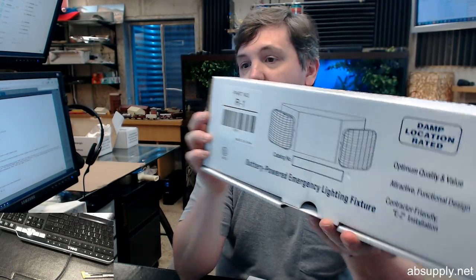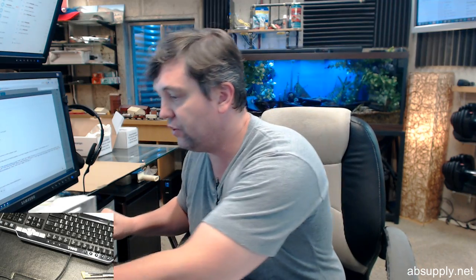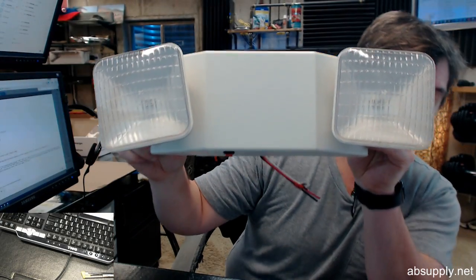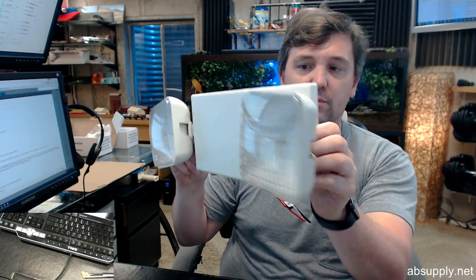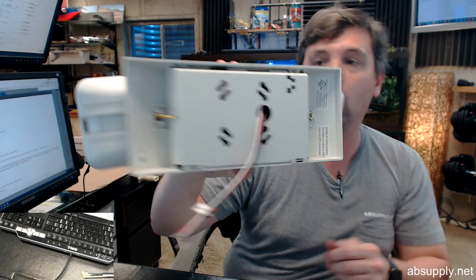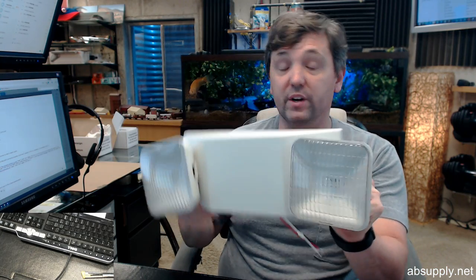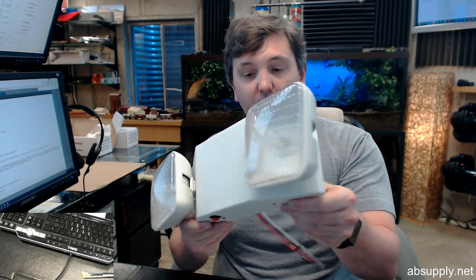This is an R1 emergency light with a pair of local lamps, 6 volt, 10.8 watt in white. I have a unit removed from the packaging for us to review. Here it is, a typical emergency light. You're going to see this in every commercial application. Code compliance requires emergency lights, which are in effect when the power goes out or otherwise tripped - the lights will go on. There's an integrated onboard battery to allow that to happen.